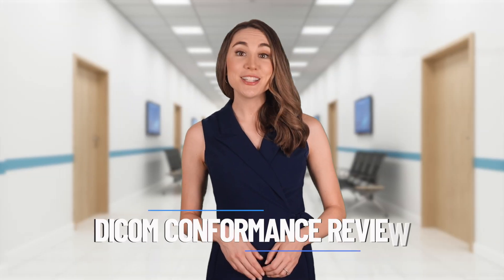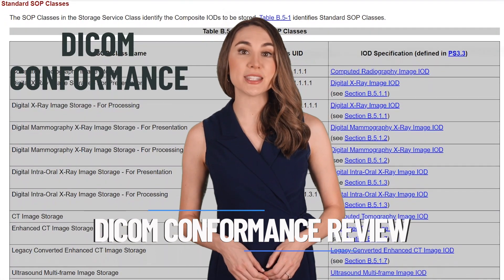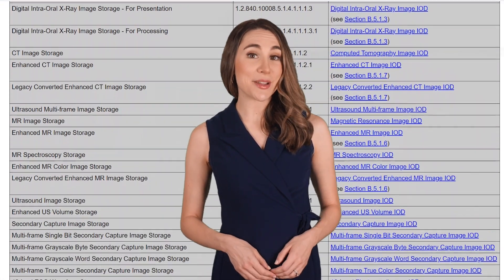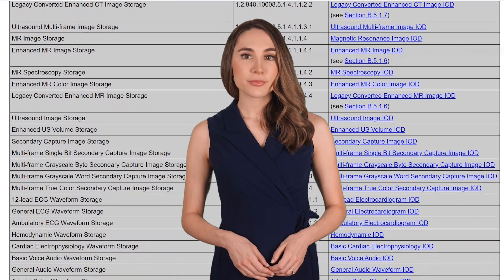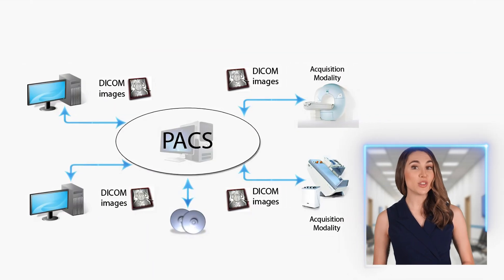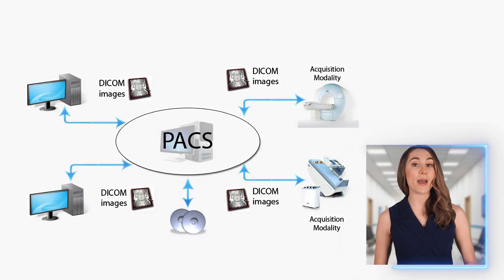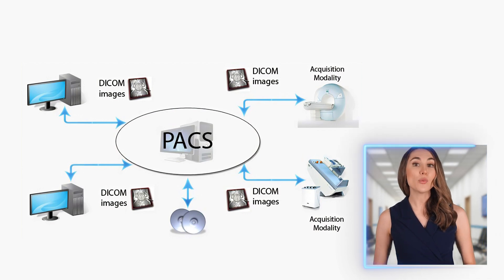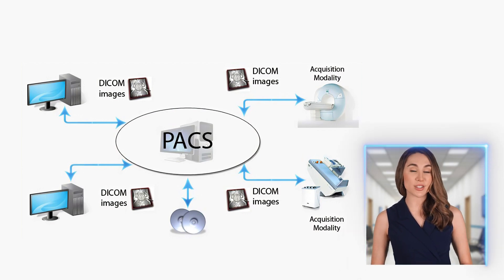Early on in the project, make time to review the DICOM conformance statement of the new scanner — that is, if you are given enough lead time. Wishful thinking, right? This document outlines which SOP classes the scanner uses for image storage, query, retrieve, and worklist. You'll want to compare this with your PACS conformance statement to ensure compatibility. If there's a mismatch in SOP classes, work with the CT vendor to adjust the scanner's configuration.